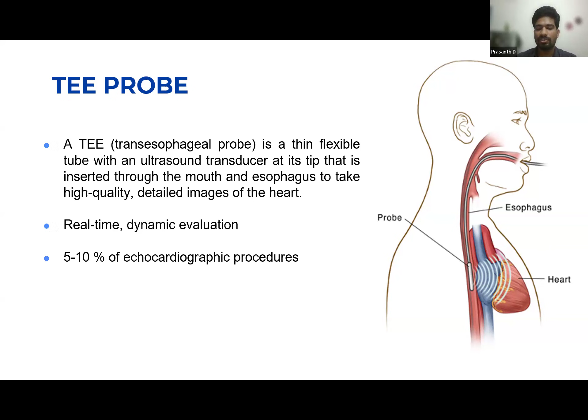So this is the transesophageal echo probe, where we can see the transducer lens at the tip, and the bending portion seen above that, and one flexible shaft along with the control housing. The control housing has the transducer control. Two wheels will be there, one larger inner wheel and a smaller outer wheel. And then the system cable, which is connected to the echocardiography machine, that is called the connector side.